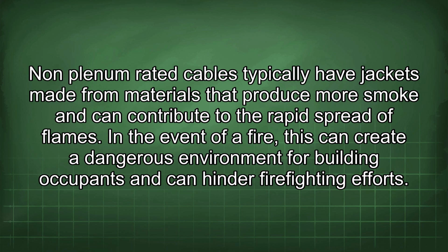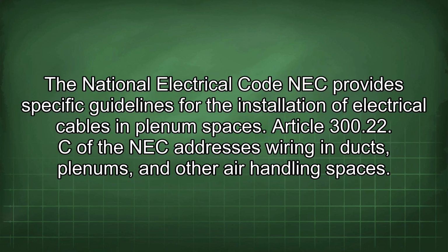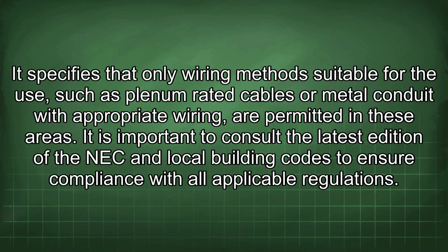can hinder firefighting efforts. The National Electrical Code (NEC) provides specific guidelines for the installation of electrical cables in plenum spaces. Article 300.22(C) of the NEC addresses wiring in ducts, plenums, and other air handling spaces. It specifies that only wiring methods suitable for the use, such as plenum-rated cables or metal conduit with appropriate wiring, are permitted in these areas.